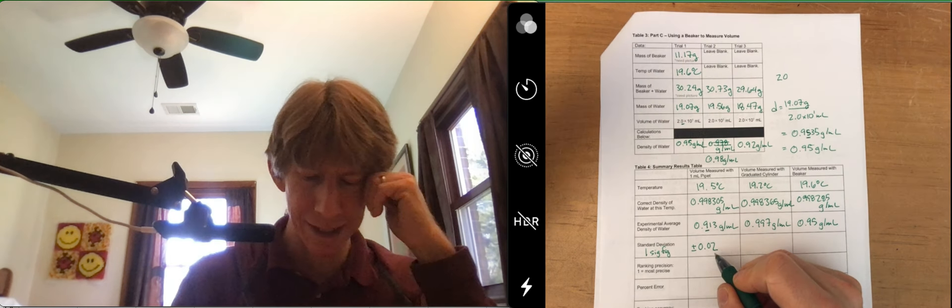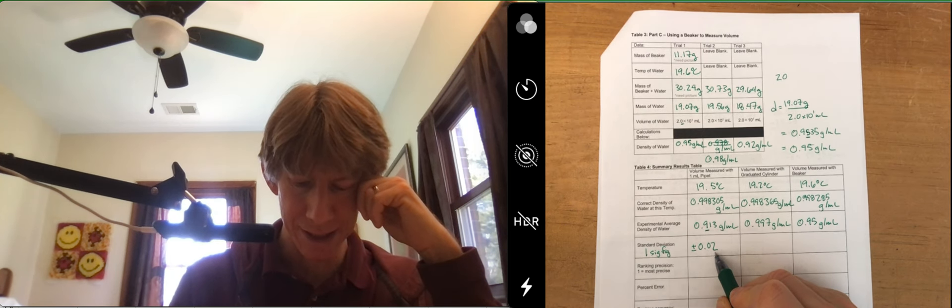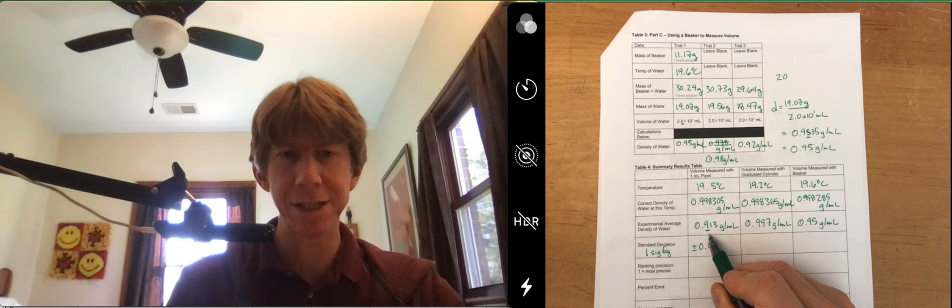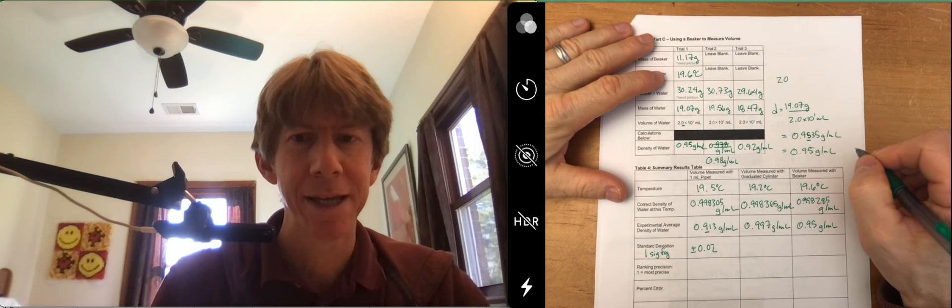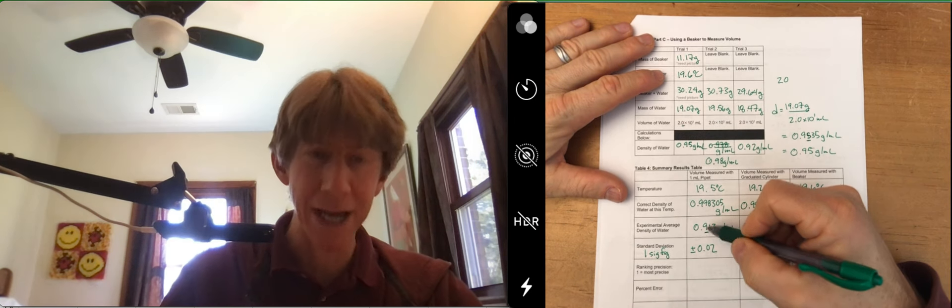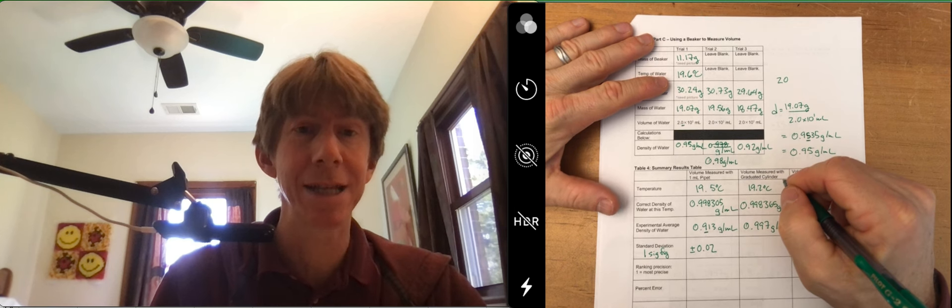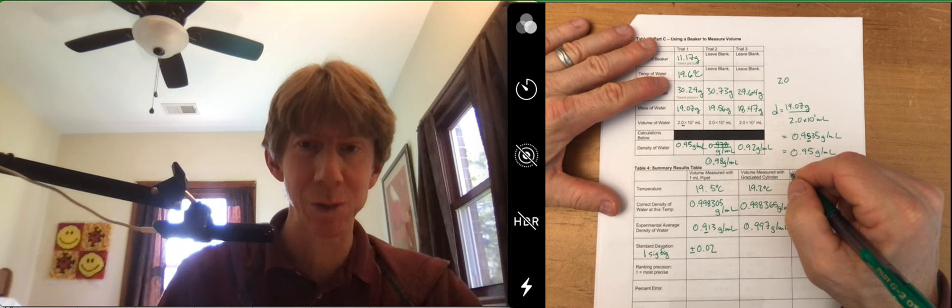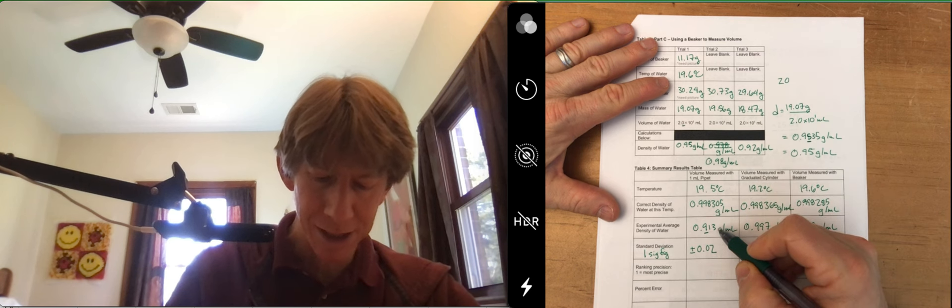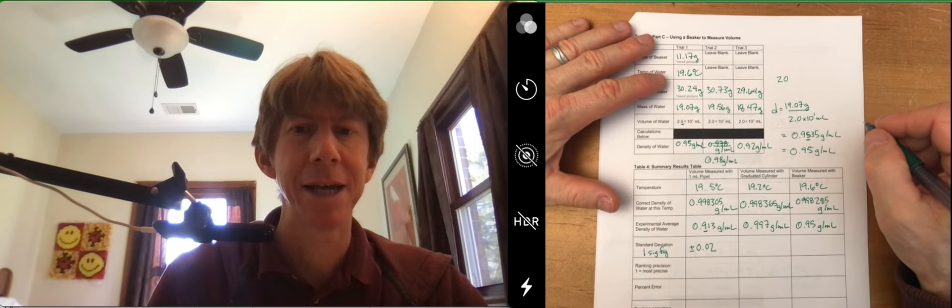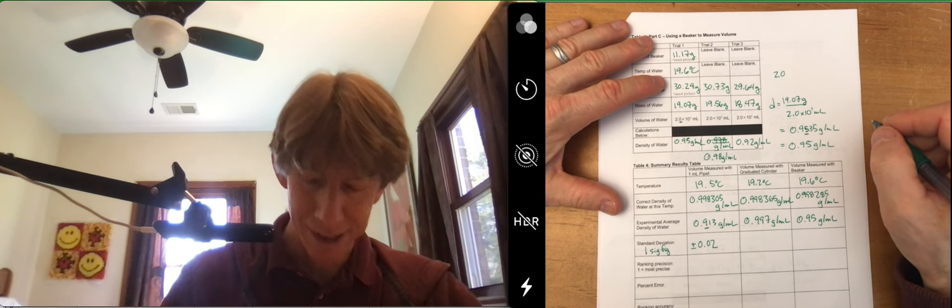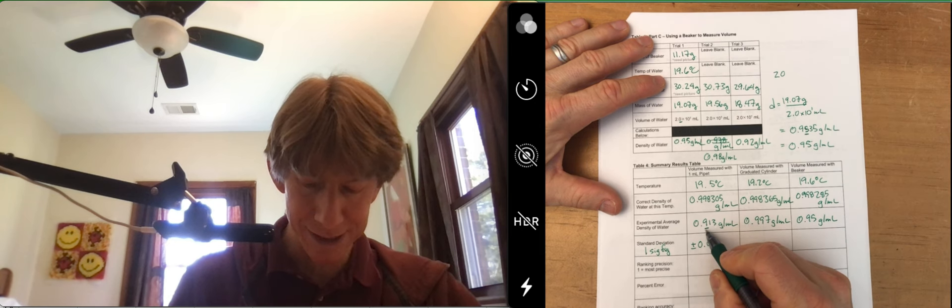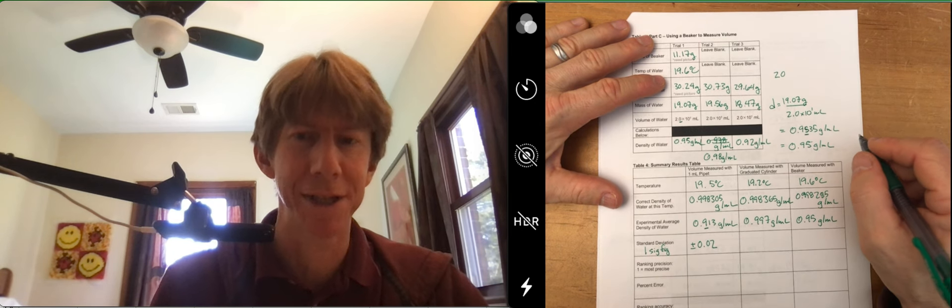And what's interesting is that this is in the hundredths place, but we only have one sig fig in the tenths place. And this fact, when I realized this, is what led to lab number two. So you're going to be doing lab number two. We're actually going to be calibrating the one milliliter pipette.